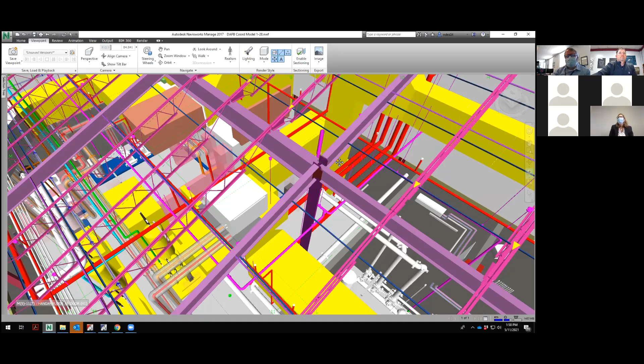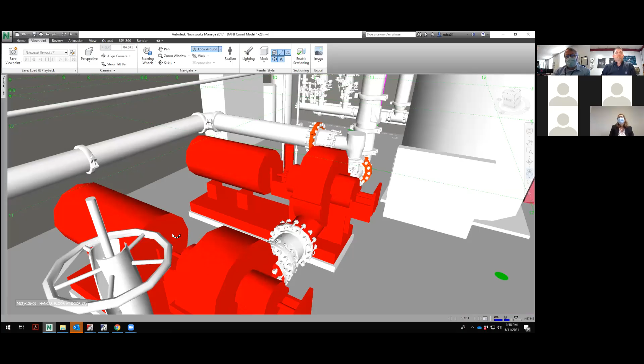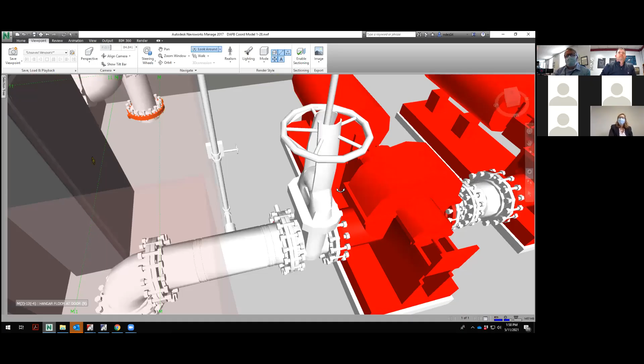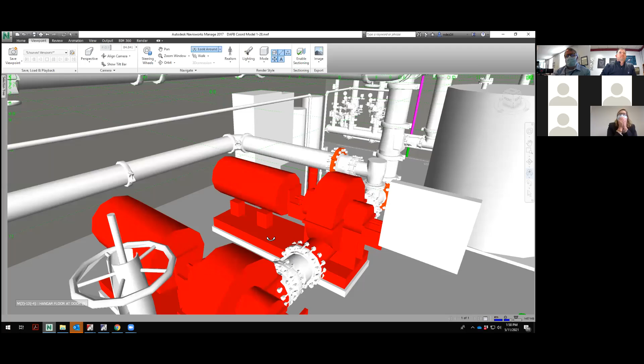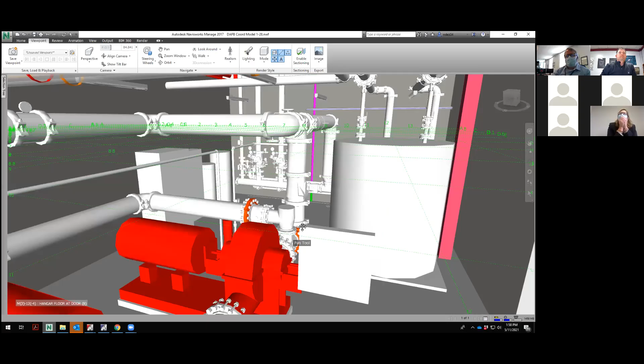These are what they call fire pumps. Since the foam system is so hydraulically demanding, it needs a lot of water very quickly. These fire pumps boost the city pressure coming in, because that wouldn't be nearly enough. They boost pressure up to about 270 PSI, which is a lot of pressure per square inch, and it puts it out through those generators within a minute's time. So it's very fast, a lot of pressure very quickly.